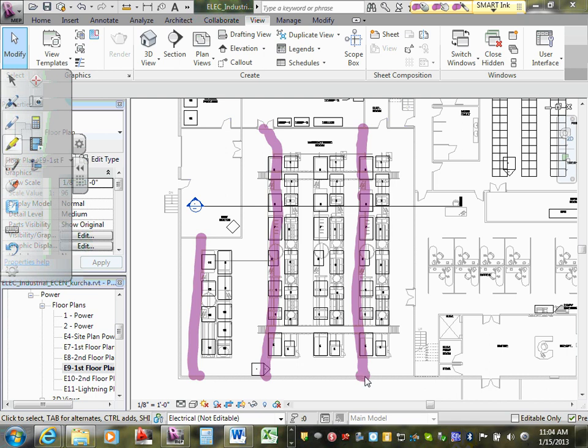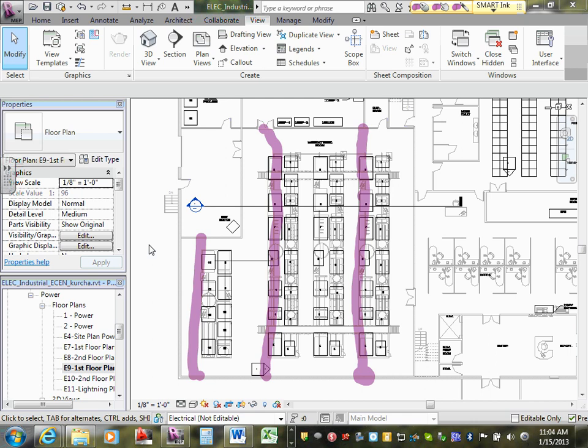What's the height that we placed them at? Below the ceiling, anywhere you can get a clear line of sight. If it's straight up to the deck, yeah, exactly. If you skim above the area, you're not going to have stratification, you're not going to have to worry about that in this area, because the smoke has to get up to that area, it's going to be above the sheet. It's not going to stratify. Not typically. They can.